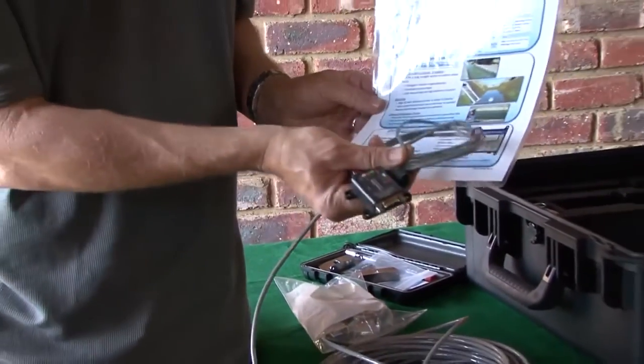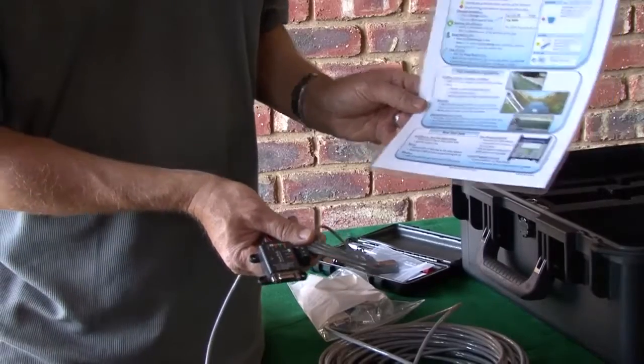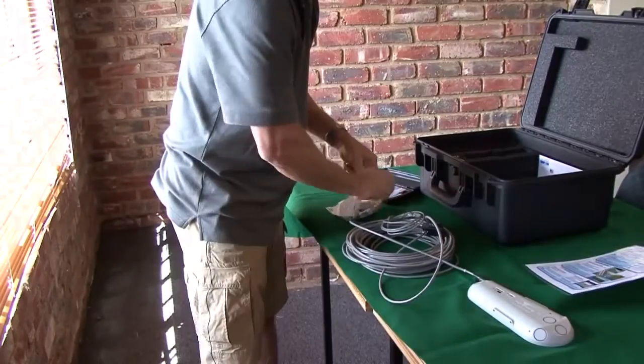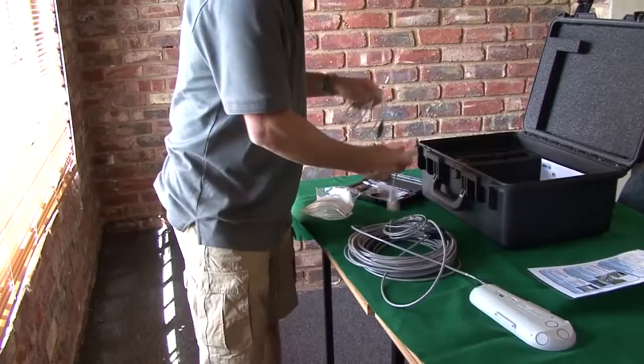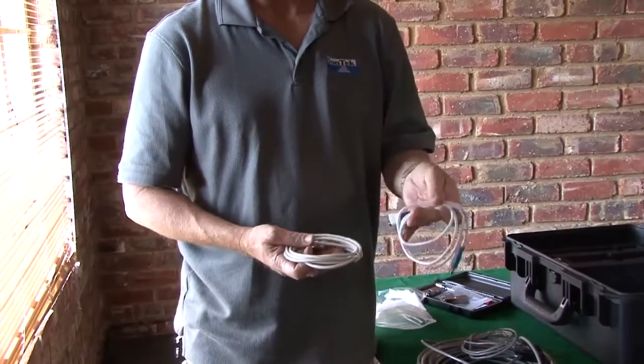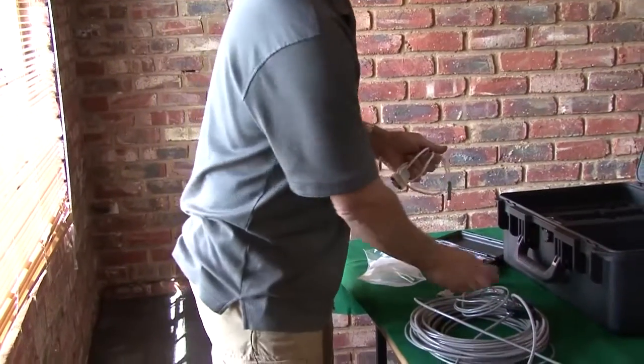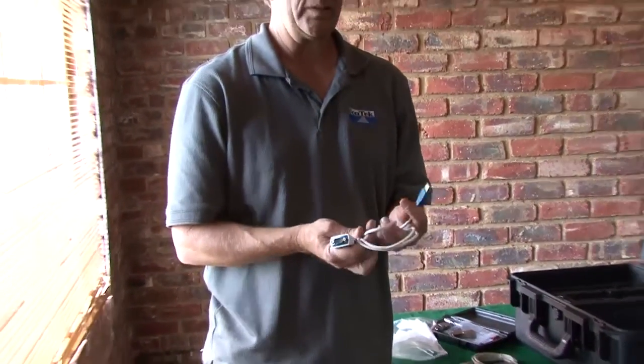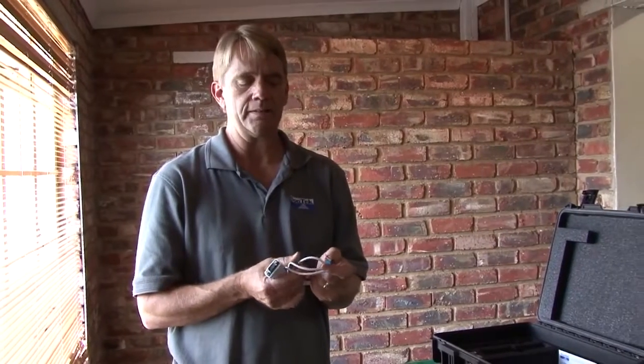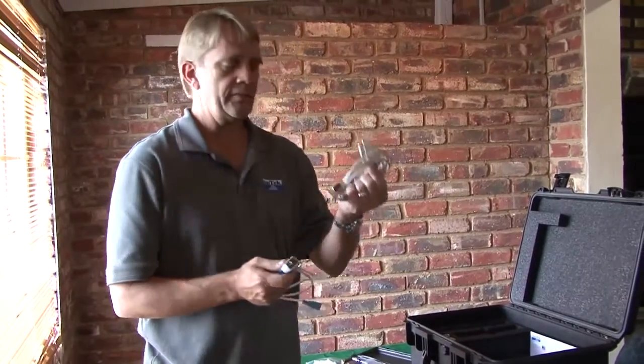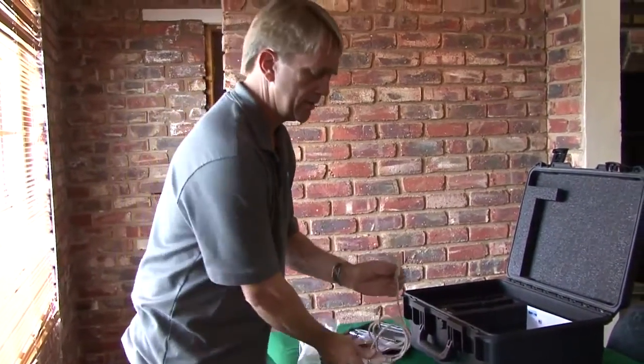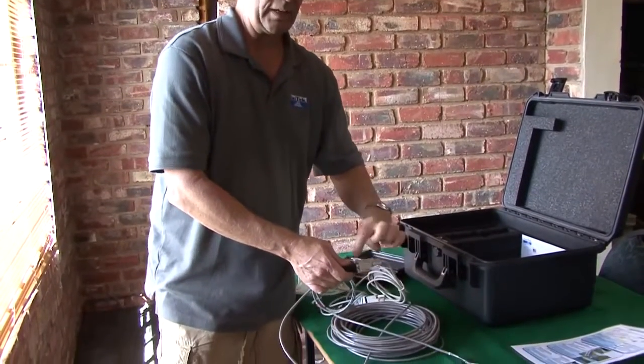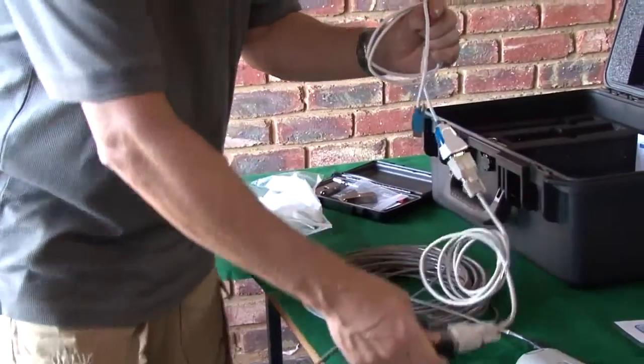If you order the real-time display, basically everything on the real-time display is in this little junction module here, with the addition of the display and the 4 to 20 outputs. To actually talk to the device with our computer, your IQ should come with the RS-232 setup: a USB to 232 connector and an RS-232 cable. We always like to connect our computers using this RS-232 USB converter. Number one, it makes the communication much more reliable. COM ports on laptops tend to vary in quality, so we've provided one of these just to minimize the problems that may arise with the COM ports. Also, the cable plugs in here to give you a little more reach to the device. Here's our communication. This also can provide a Modbus communication as well. So here's all our connections sitting right here.